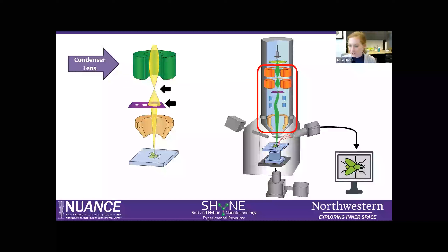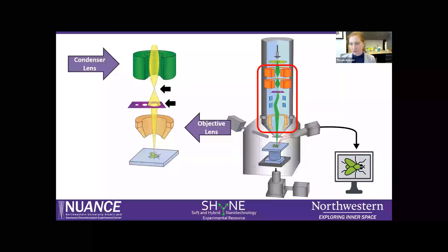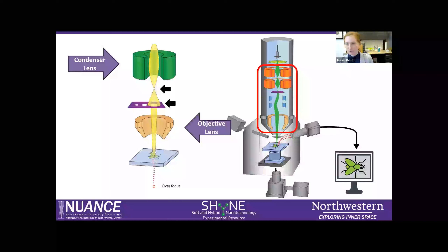After the condenser lens and objective lens aperture, the beam passes through the objective lens. Changing the current through the objective lens changes the final crossover of the beam at the specimen's surface. When you're at the microscope and turn the focus knob, you're changing the crossover height to either under-focus or over-focus. You want the beam to cross over at the sample surface for best focus, which is where you get the smallest probe.